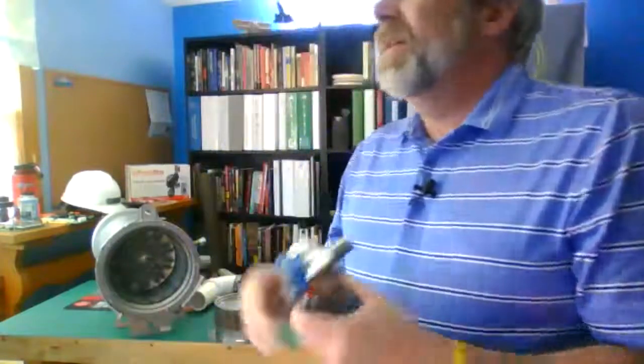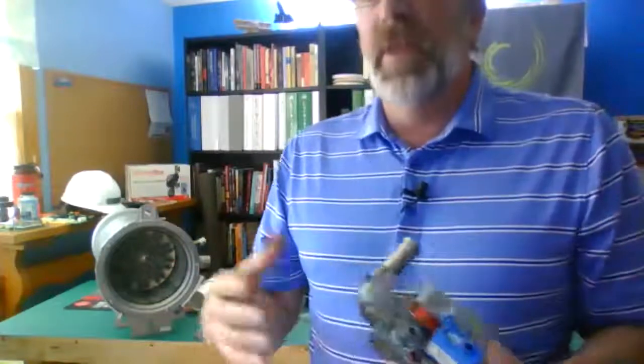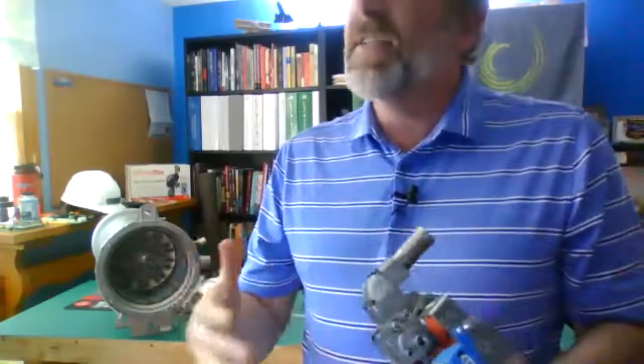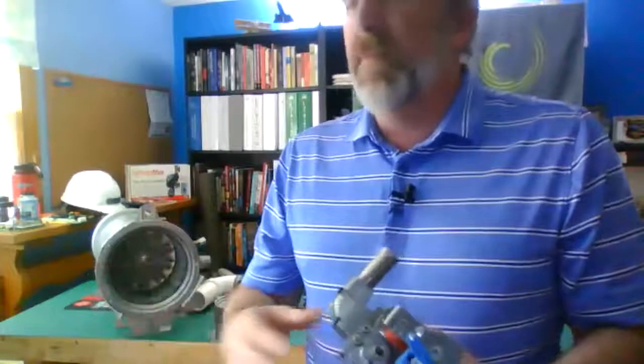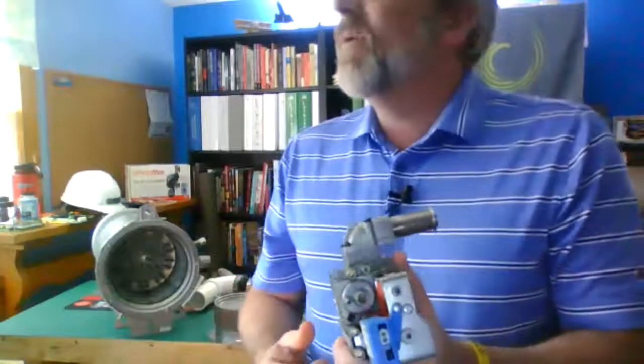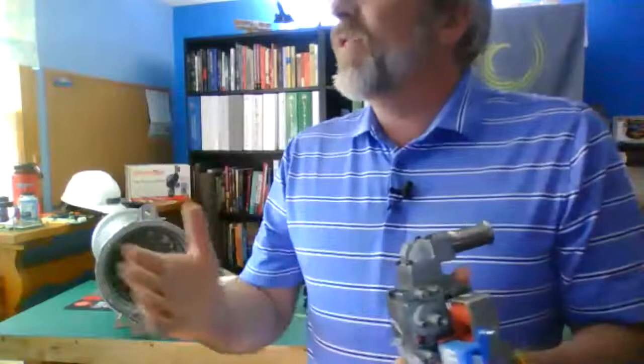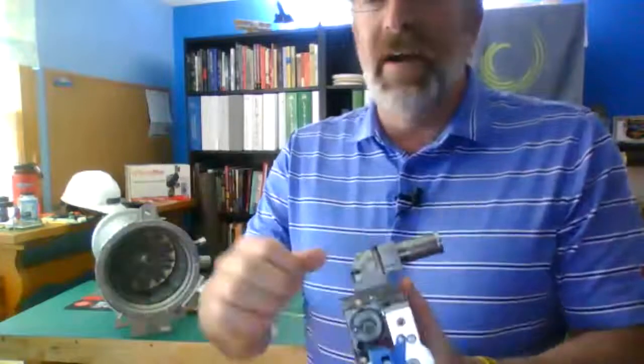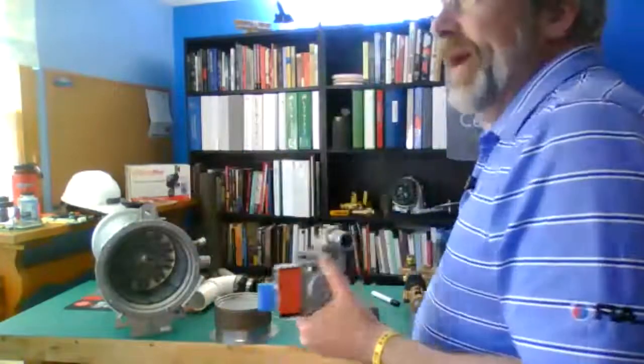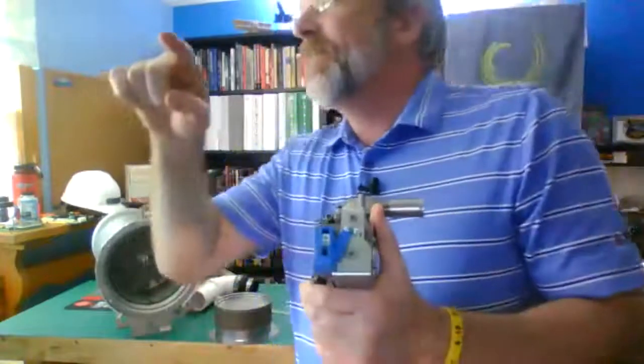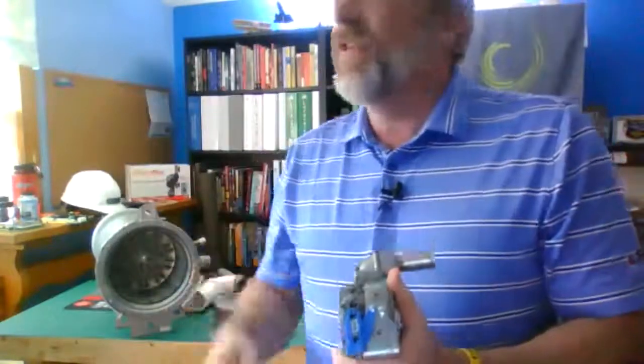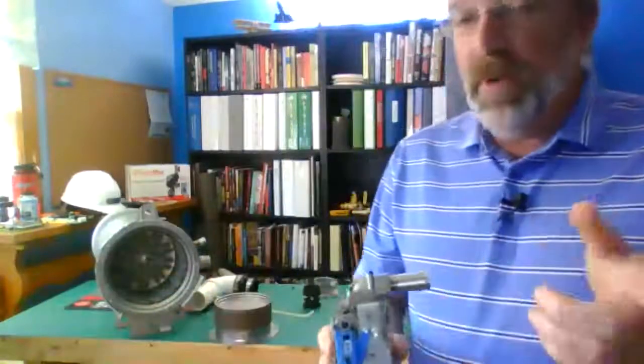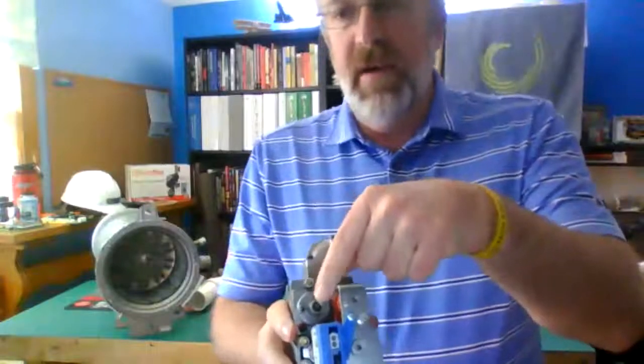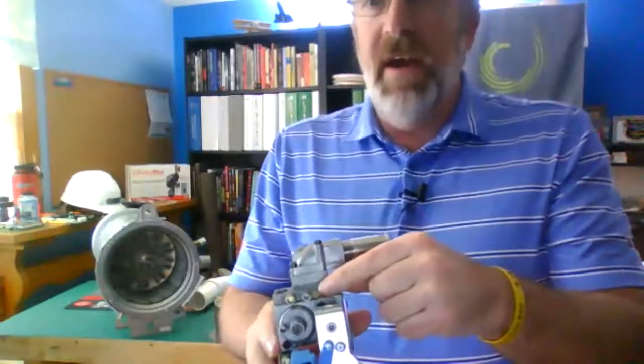Now, if you're chasing a noise complaint with a boiler, find out where that noise is in the combustion. Use your service mode, adjust your gas valve right to that spot in the combustion range, and make an adjustment right there. So they say it's at 30%. Let's go to 30%. Let's get right there. You see if we're dropping off there, and let's adjust right there, and let's check our numbers. You can always adjust in the middle, but really important, low fire here, high fire here.